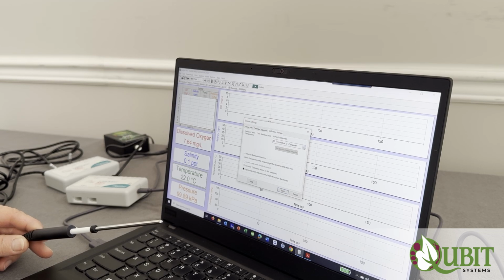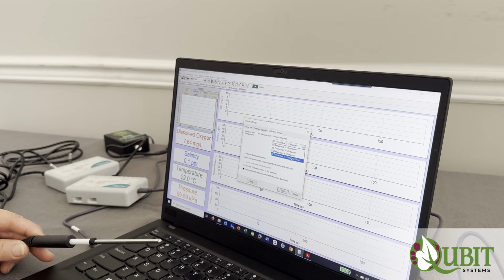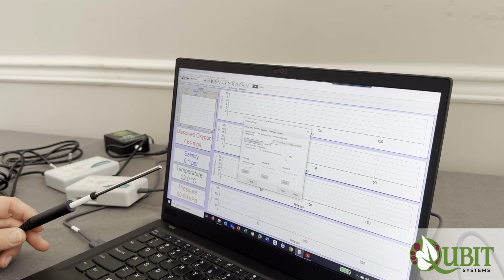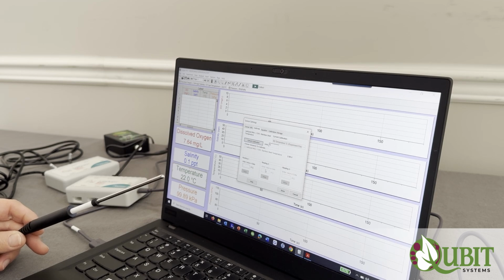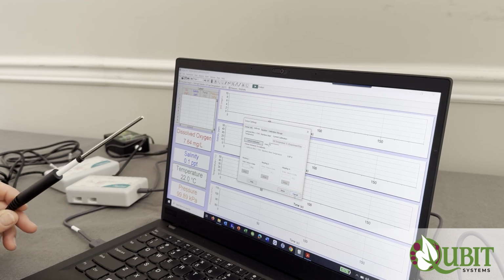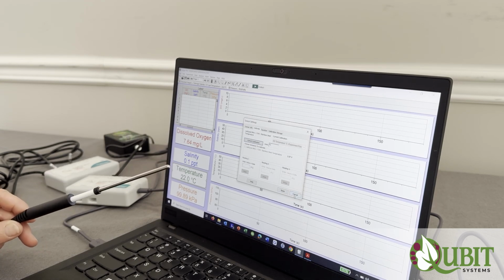So one has to select here, temperature experimental file, here experimental file as well, and then one can proceed to calibrate. And once you say calibrate now, you will see a voltage reading for that specific temperature, and you enter the temperature data here, click keep, then go to reading 2, keep, reading 3, keep, and then at the end you click done. I'm not going to do that here because I'm not trying to change this calibration.